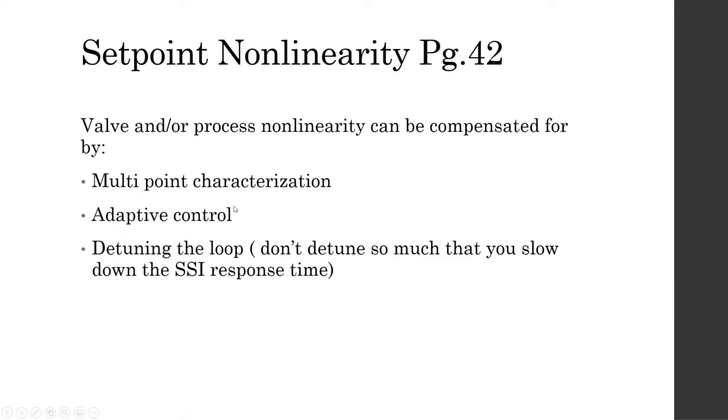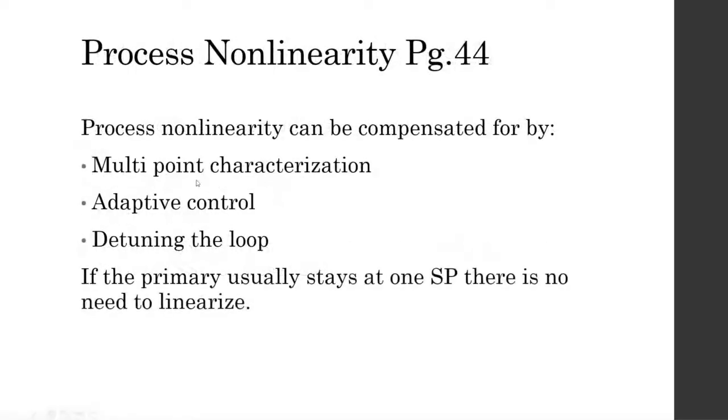So first, set point nonlinearities, pretty standard toolbox. Process nonlinearities, same toolbox. So characterization, adaptive control, detuning, same practices in order to linearize both scenarios here. If the primary usually stays at one set point, you don't really have a problem with linearization, so you don't have to worry about it.